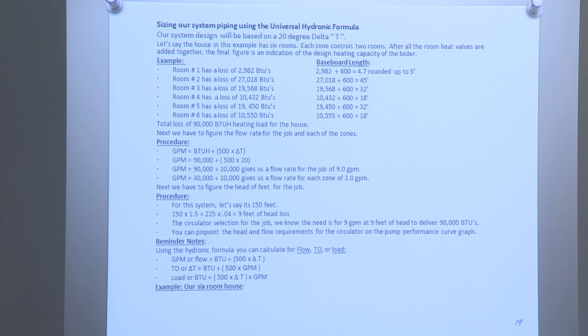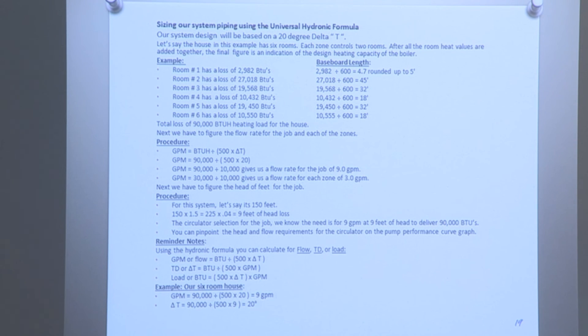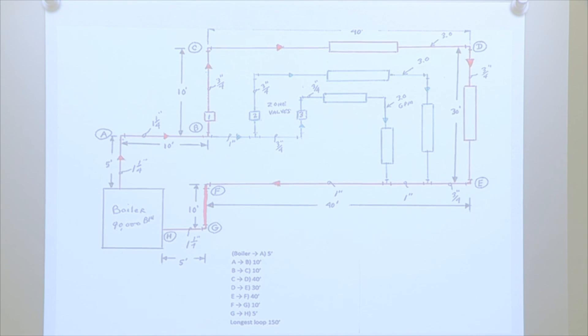Here is the six-room house example verified. We had 90,000 BTUs; using the formula 500 times 20 gave us 9 gallons per minute flow rate. Checking delta T: 90,000 divided by 500 times 9 equals 20 degrees. And checking BTU: 500 times 20 times 9 equals 90,000 BTUs — all confirmed. Here's the drawing showing the longest loop method, with zones, pipe sizing, the longest loop shown in red and the two shorter loops in green.